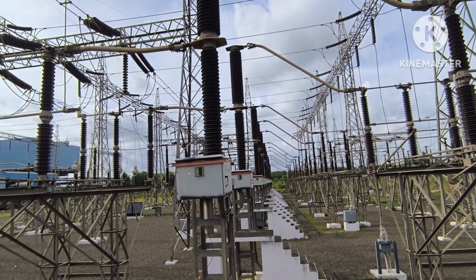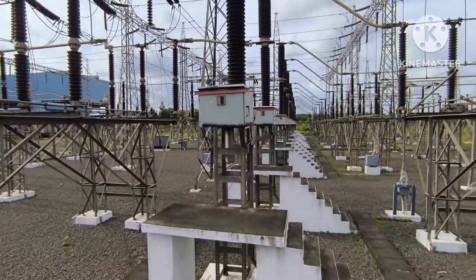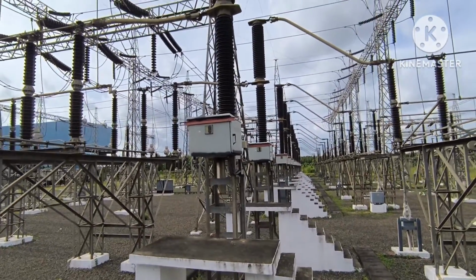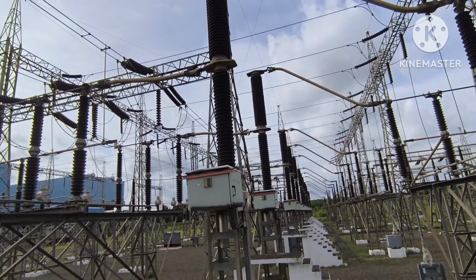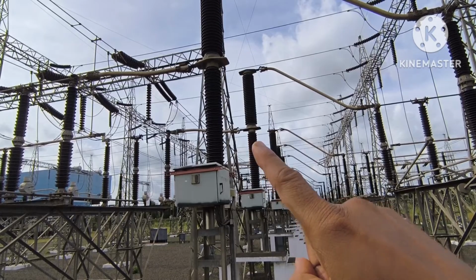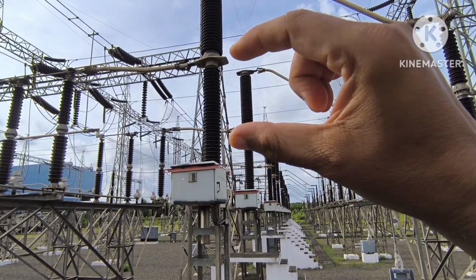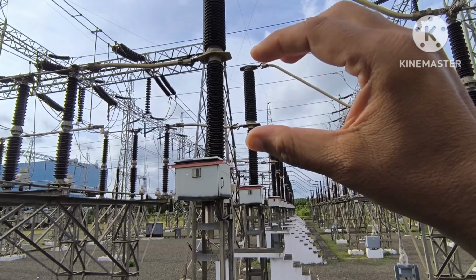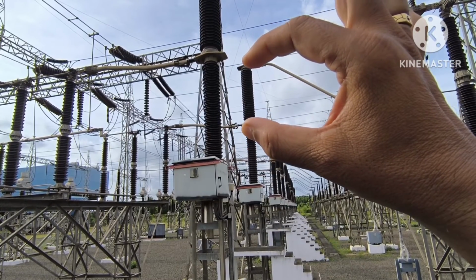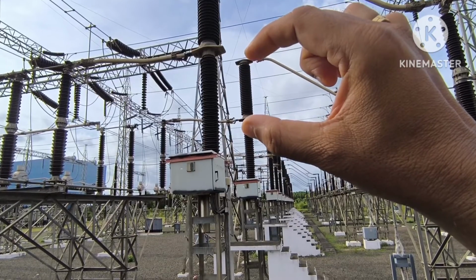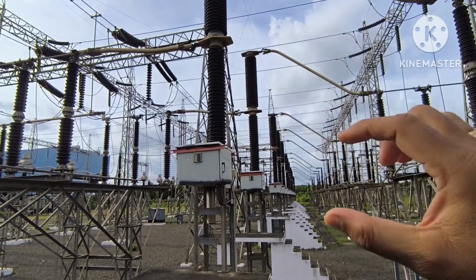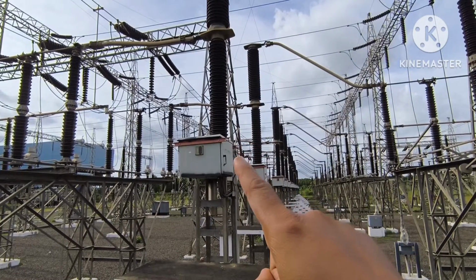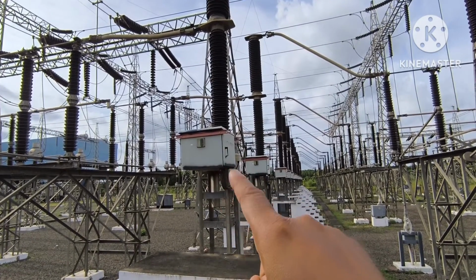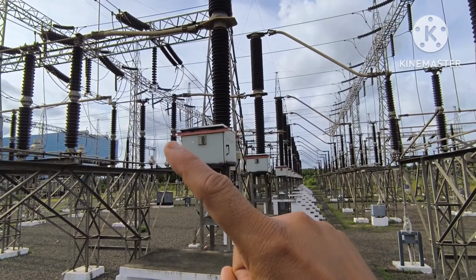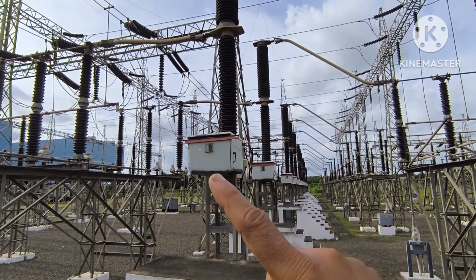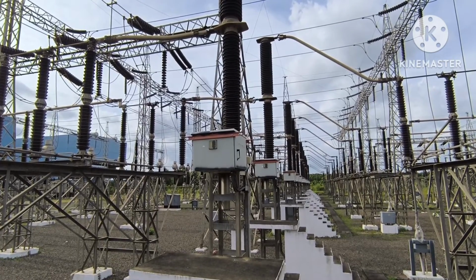Each pole is an independent pole operated circuit breaker, so you will find one circuit breaker in each phase. This is called the middle pad and this is called the top pad. The contact separation during breaker operation, whether close or open, the fixed contact and moving contact operation, will happen inside this portion, top to middle portions. This is the mechanism box. This is the mechanism for B phase, Y phase, and I am standing in the R phase. So each phase has one mechanism.